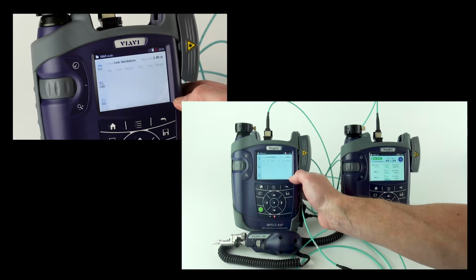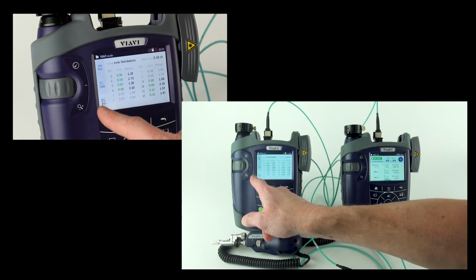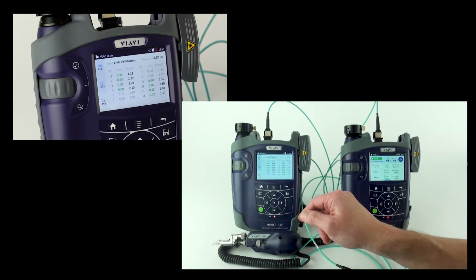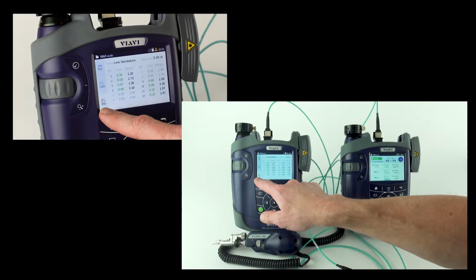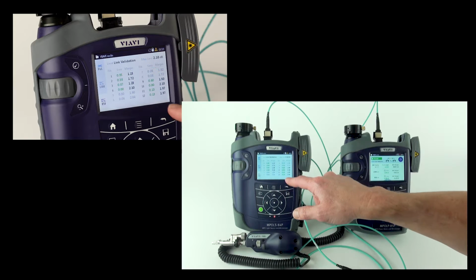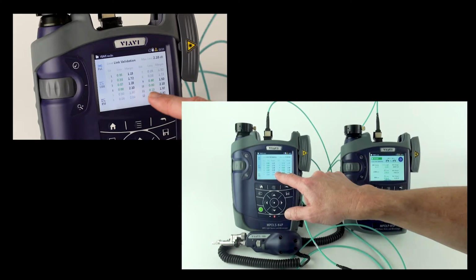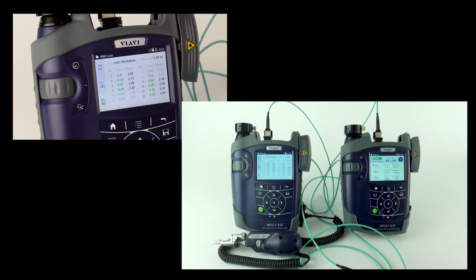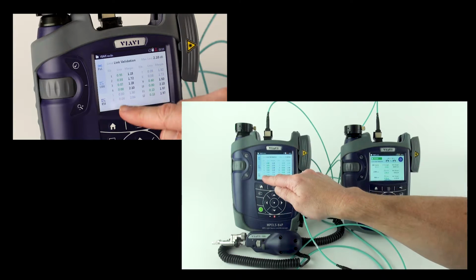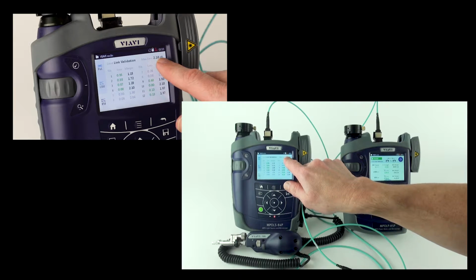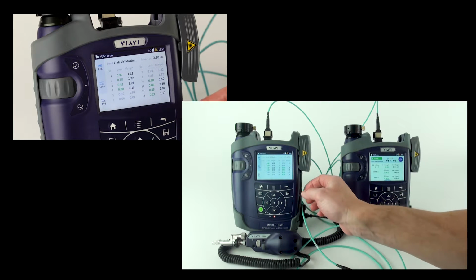And if I wanted to go into detail, I can go into detail and I can go between my different wavelengths and my polarity. When I'm looking at my detail, I now see all my fibers. You notice that the 4 in the middle are grayed out, and that's because I set it to ignore those for pass-fail analysis. I see what my loss is of each of the fibers, I see what my margin is, and at the top right, I see what my limit setting was.